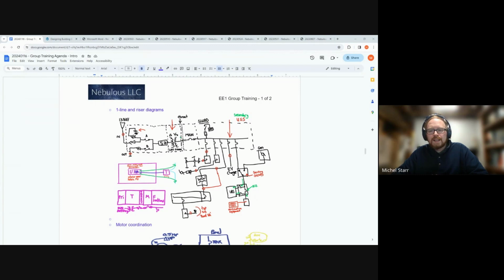So I would say, and I'll say we as in one of those that probably have put out drawings, we have tried really hard, but it's not always coordinated to the exact degree that you'd like. So there will be that case. First, know that whenever we open drawings, and I know that I have this as well when I open drawings, especially from completed projects, they're pretty intimidating. And you're like, where do I start? But they were completed by humans that had one way of doing it that may be consistent with the industry. So it's not uncommon that the panel schedules will, first, maybe they're missing.